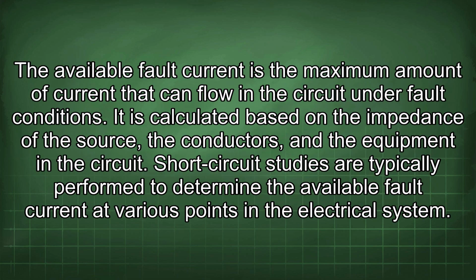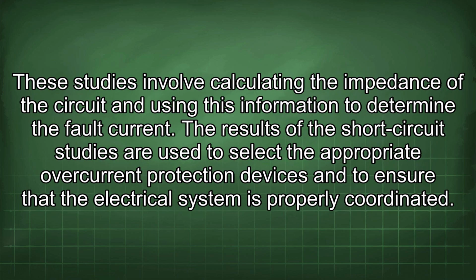The available fault current is the maximum amount of current that can flow in the circuit under fault conditions. It is calculated based on the impedance of the source, the conductors, and the equipment in the circuit. Short circuit studies are typically performed to determine the available fault current at various points in the electrical system. These studies involve calculating the impedance of the circuit and using this information to determine the fault current. The results of the short circuit studies are used to select the appropriate overcurrent protection devices and to ensure that the electrical system is properly coordinated.